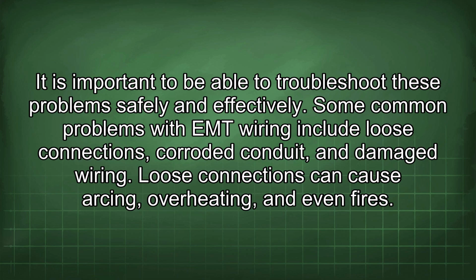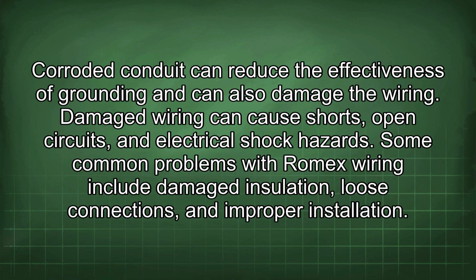Some common problems with EMT wiring include loose connections, corroded conduit, and damaged wiring. Loose connections can cause arcing, overheating, and even fires. Corroded conduit can reduce the effectiveness of grounding and can also damage the wiring. Damaged wiring can cause shorts, open circuits, and electrical shock hazards.